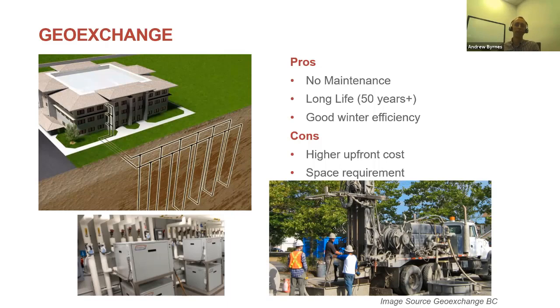Geoexchange has a number of advantages: it's a great energy source with very little maintenance, and extremely long life since the piping is all plastic and covered underground. It also gives good winter efficiency, especially in colder parts of the province where air source heat pumps can suffer lower efficiency at very cold temperatures.